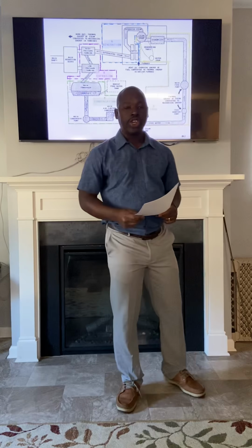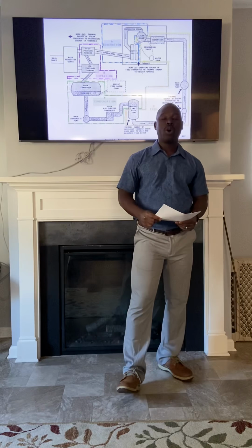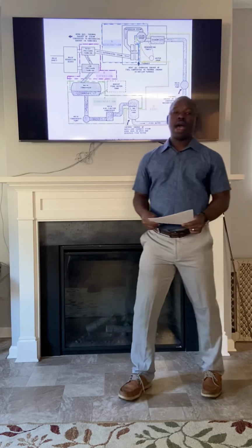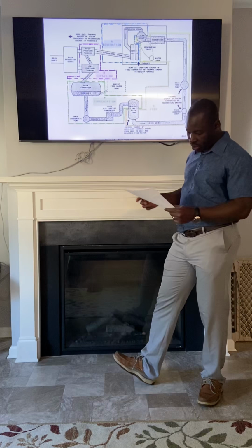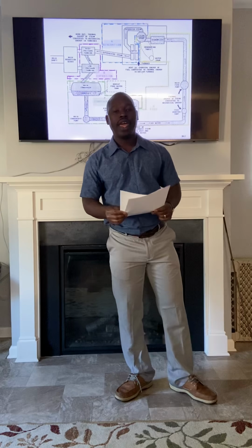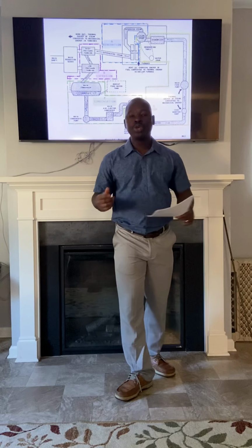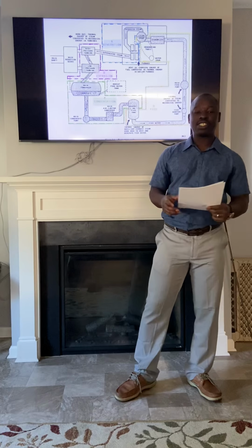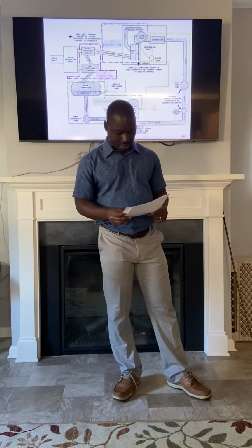The main condenser is a heat exchanger with several tubes containing cold water. As exhaust steam comes in contact with the cold tubes, it gets condensed. The condenser operates under vacuum between 27 and 30 inches of mercury, which reduces the condensation temperature and makes the system work efficiently.